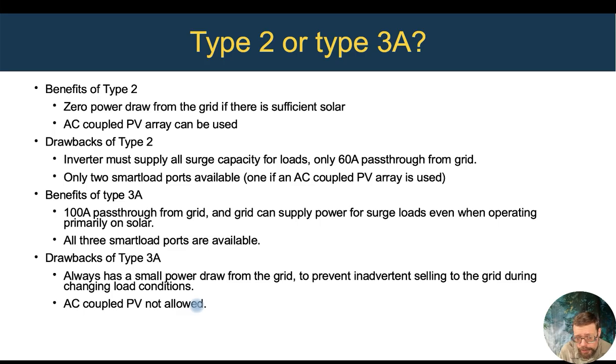If you want a lot of smart load ports to control various things, you have fewer of them available on a Type 2 because you're using one of them up as your AC grid input. And if you've got an AC coupled PV array, there's another one used up. You've only got your smart load 3 left. If you do a Type 3A, you've got all 3 smart load ports available, so you get a little more diversity of load control. So some differences where you do have an interconnection agreement. If you've got a big enough system and small enough loads, it may still make sense to do a Type 2 rather than a Type 3A.